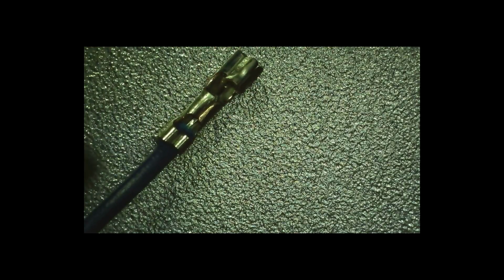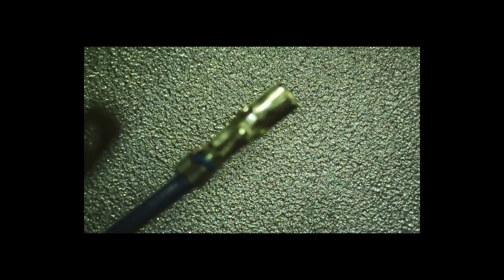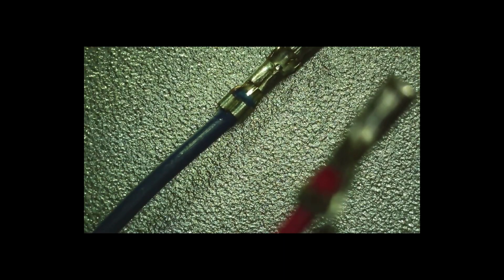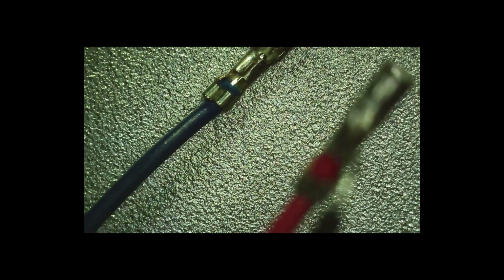So that was the blue one. Give a good look, Lou. I mean, it's okay if you're not completely butted up against the insulator, but as long as the insulation is grabbed, that's more than enough. That's all you really need. That's your key to holding power, is to grab hold of the insulation. So I'm going to go and switch back to my webcam.